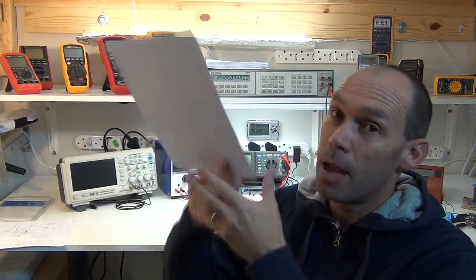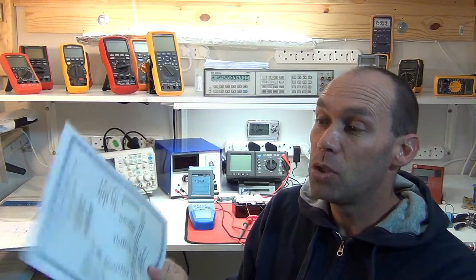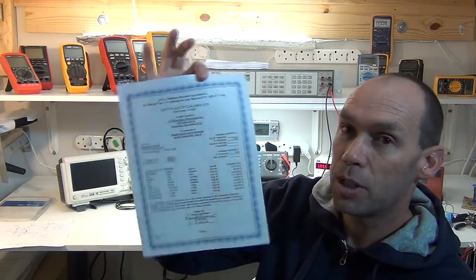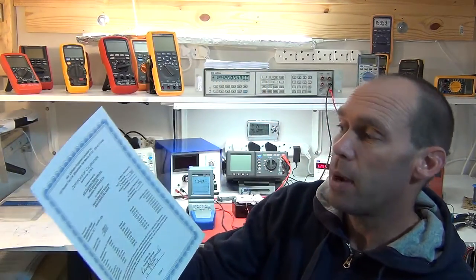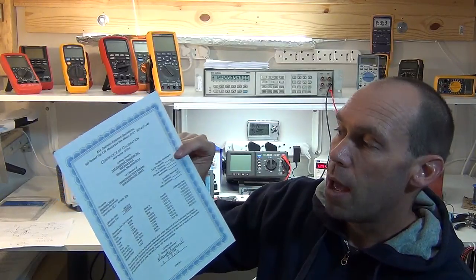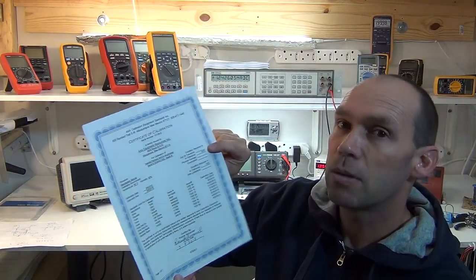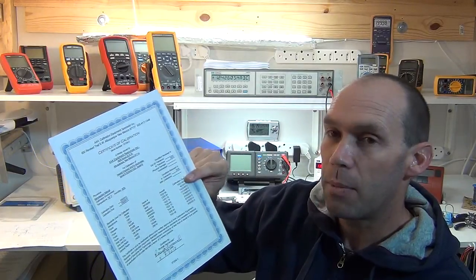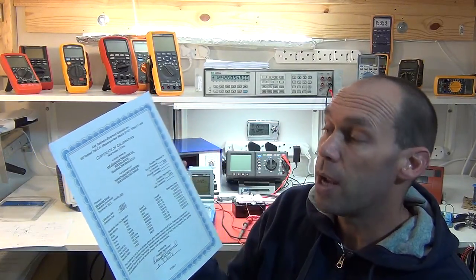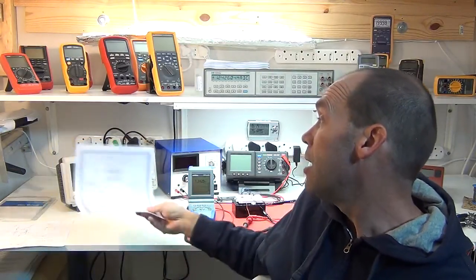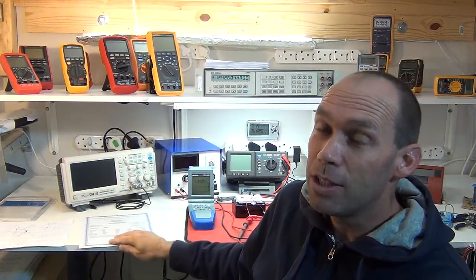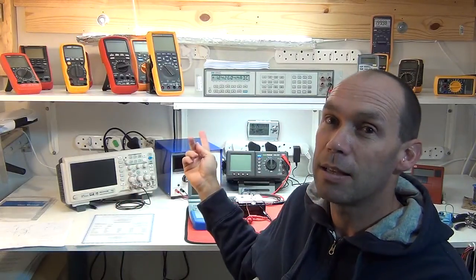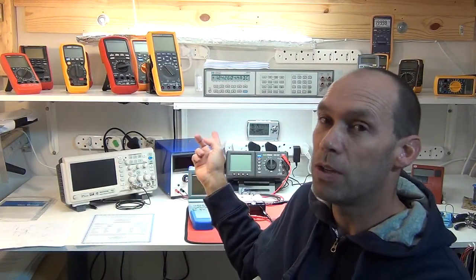Also, it was literally calibrated two days after I purchased it. I've got the certificate of calibration here. When I say calibrated, according to this, it was in tolerance when they went through all the calibration criteria, which is great news. Obviously, I can't really check it because I've got nothing accurate enough to check a 6.5/7.5 digit multimeter.